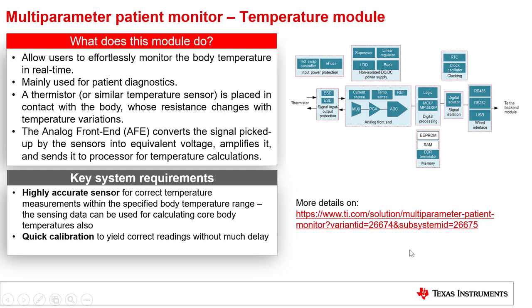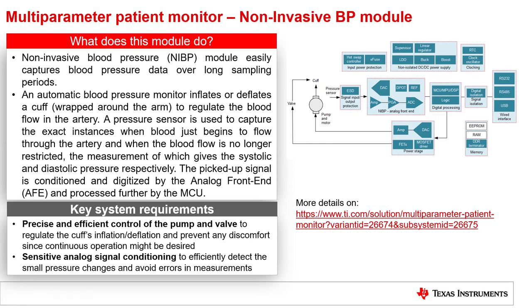The fourth module is the non-invasive blood pressure, or NIBP, module. This module easily captures blood pressure data over long sampling periods. An automatic blood pressure monitor inflates or deflates a cuff to regulate the blood flow in the artery. A pressure sensor captures the exact instance when blood just begins to flow through the artery, and when the blood flow is no longer restricted. The measurement gives the systolic and diastolic pressure, respectively. The picked-up signal is conditioned and digitized by the analog front end, or AFE, and processed further by the MCU.